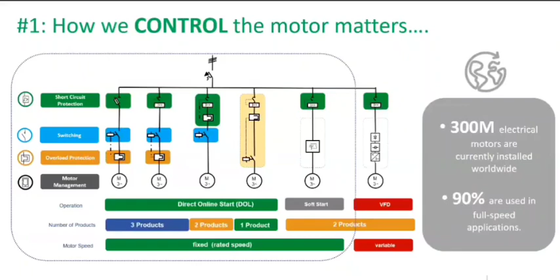For example, there is a conventional MCC. In conventional MCC, there are type coordination and product selection. As I spoke about, a standard thermal overload relay, a normal contactor, and a protection device. Similarly, if the customer wants to upgrade by one step, if they want all the detailed features, motor protection, fault differentiation, digital connect, all this is also available with our advanced MCC. And the third category is intelligent. By default, everyone is aware the intelligent MCC category is the upper part today, where we talk about communication, a lot of data, and a lot of diagnostics.